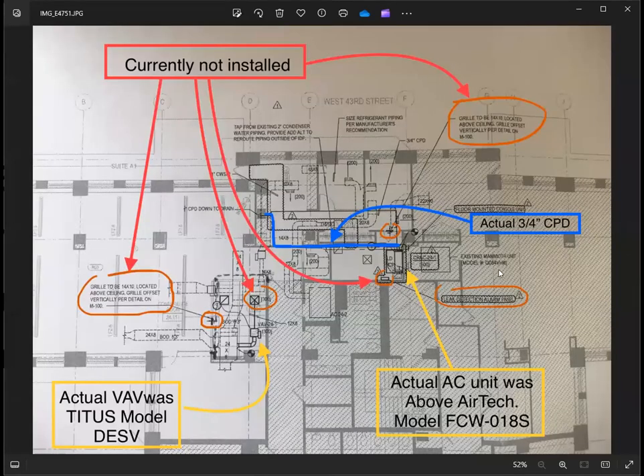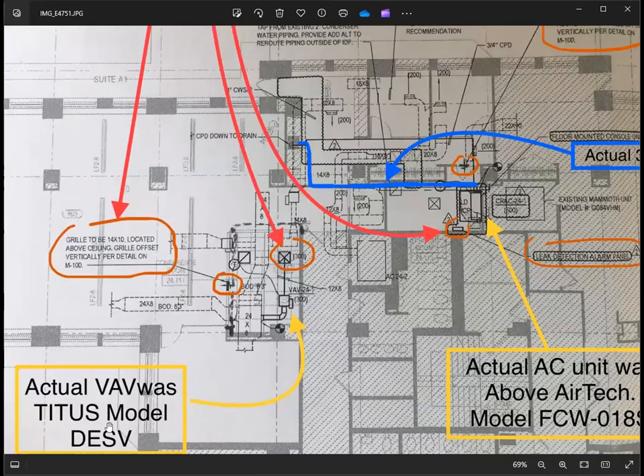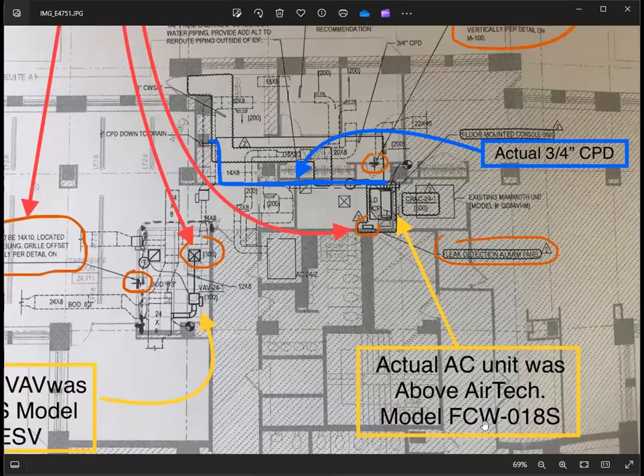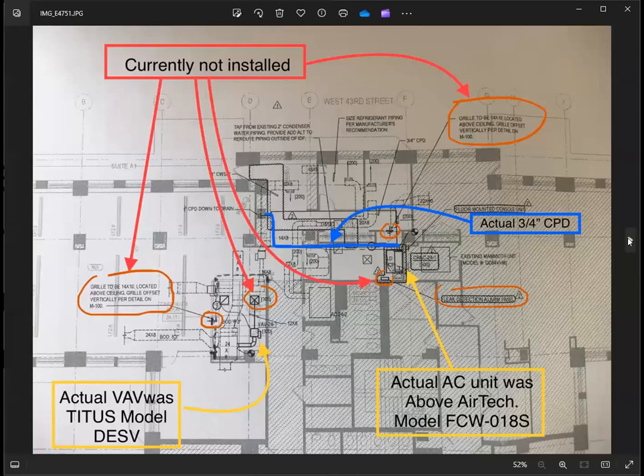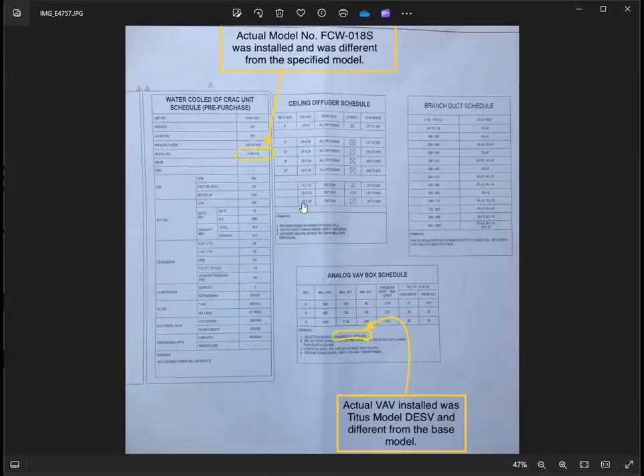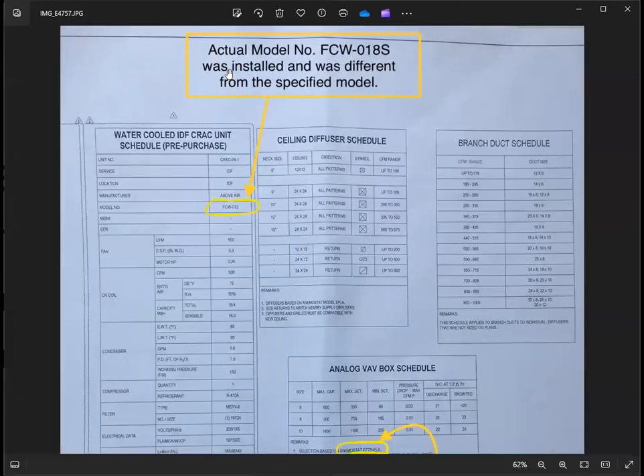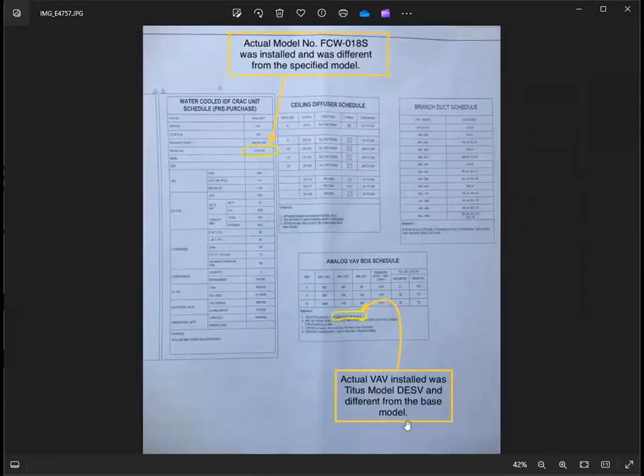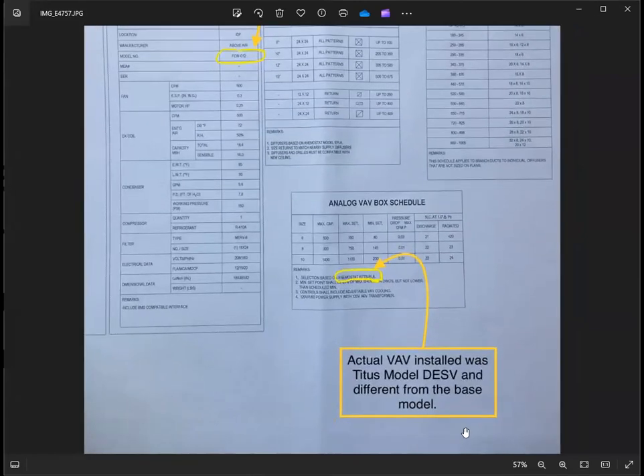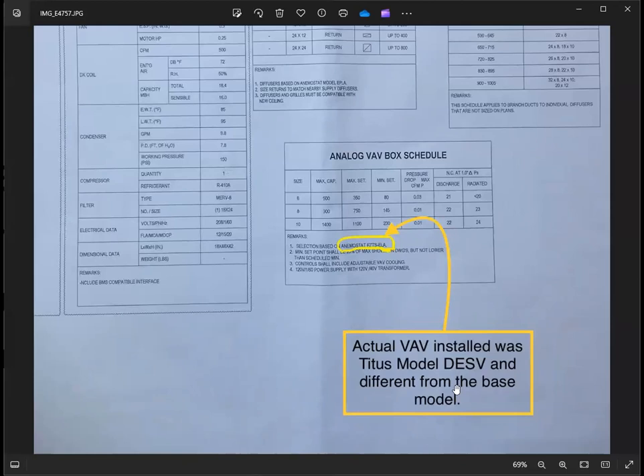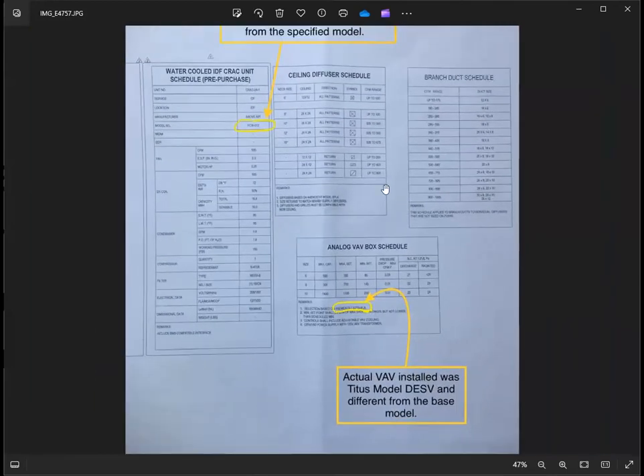And so far, these are the findings that I have marked on the drawing plan. You could do this also as a good reference, to see which one is currently installed and which one is not. And probably identify also, take note of the model numbers and manufacturer. So you could take note like this also. I noted that the unit installed was different from the specified model. So you need to acquire approved submittals to make sure that the unit is applicable for the system. And the VAV is also different, so they need to have approved submittals for it.